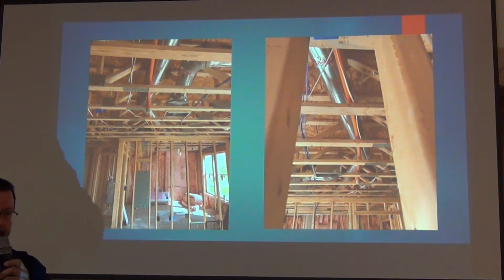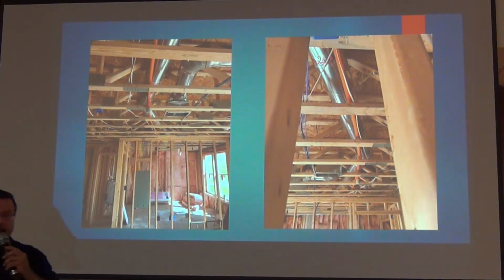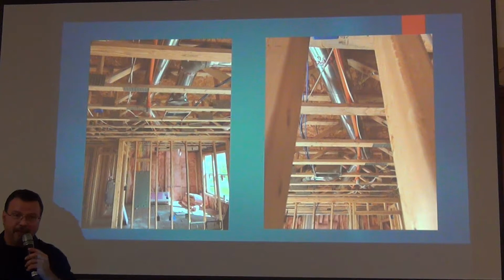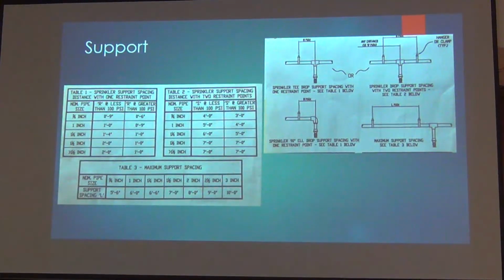Each manufacturer has suggested installation instructions, and it'll tell you how much deflection you can have on them pipes. Because they can actually deflect the pipe on purpose to reach a set space for their sprinkler spacing. It also tells you how it should be glued, which I'm gonna cover some of that too, because I've seen a lot of things. Okay? That wire right there had to be moved. That's a combustible jacket that will eat away my pipe. All right, so hang in the pipe.